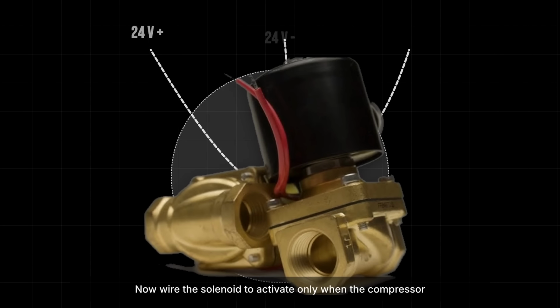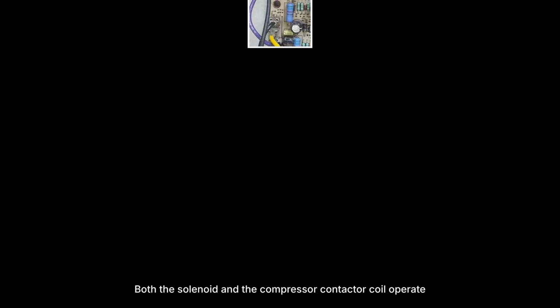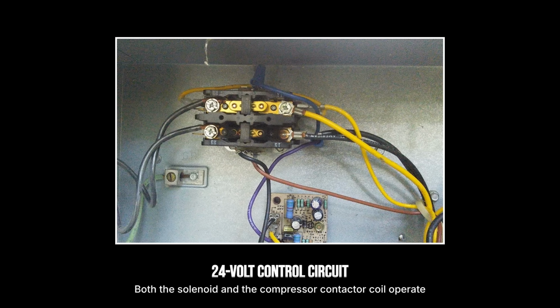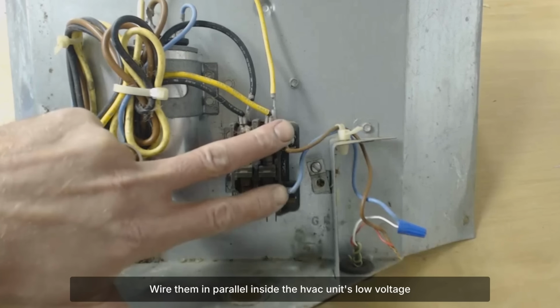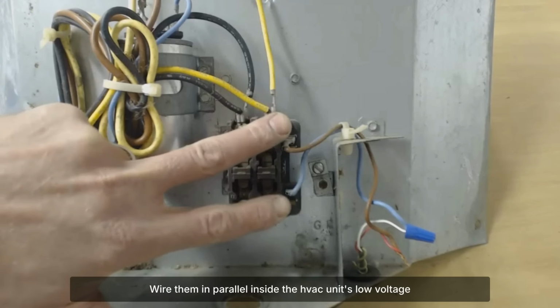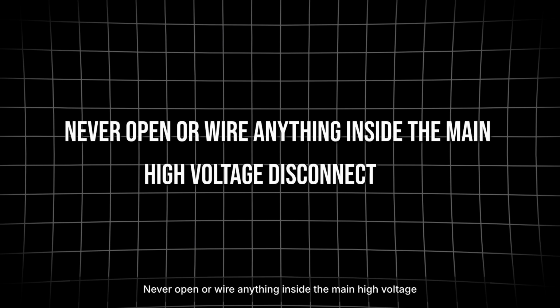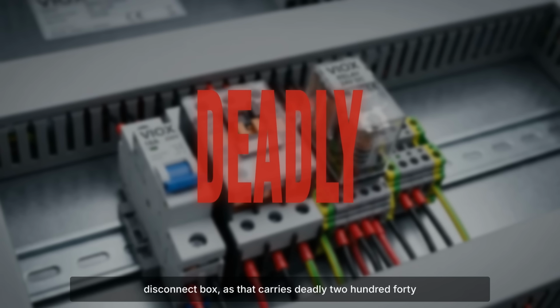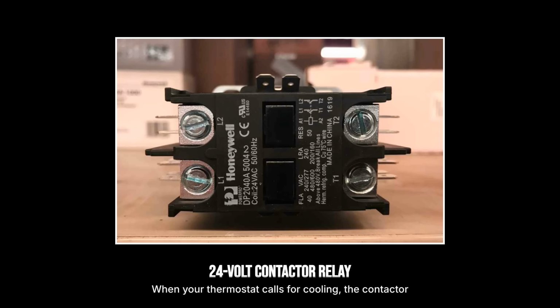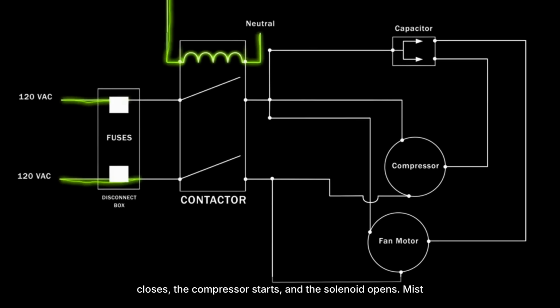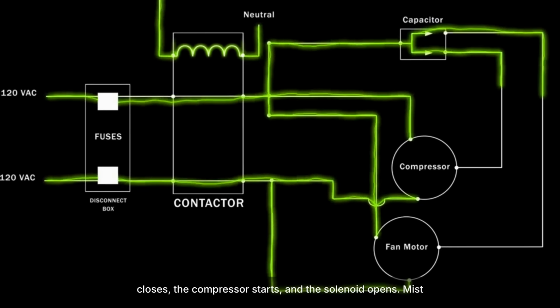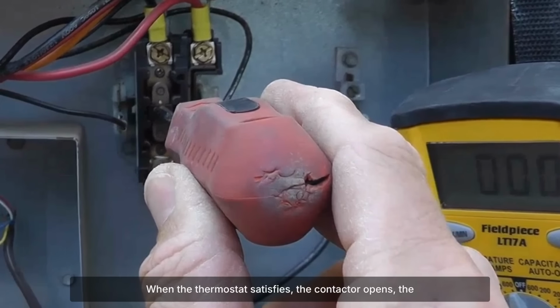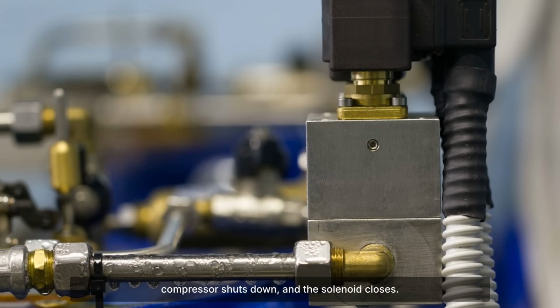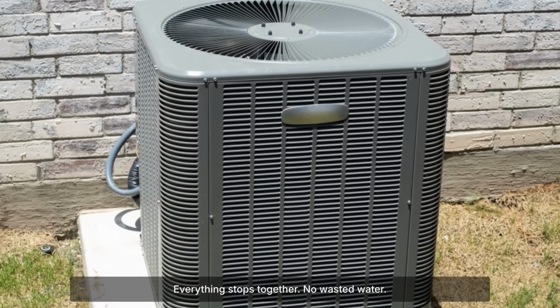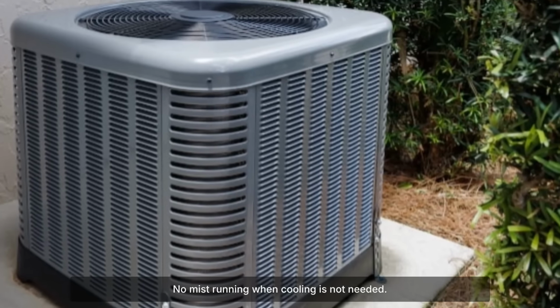Now wire the solenoid to activate only when the compressor is running. Both the solenoid and the compressor contactor coil operate on 24 volts. Wire them in parallel inside the HVAC unit's low voltage control panel. Never open or wire anything inside the main high voltage disconnect box, as that carries deadly 240 volt current. When your thermostat calls for cooling, the contactor closes, the compressor starts, and the solenoid opens. Mist flows. When the thermostat satisfies, the contactor opens, the compressor shuts down, and the solenoid closes. Everything stops together. No wasted water, no mist running when cooling is not needed.